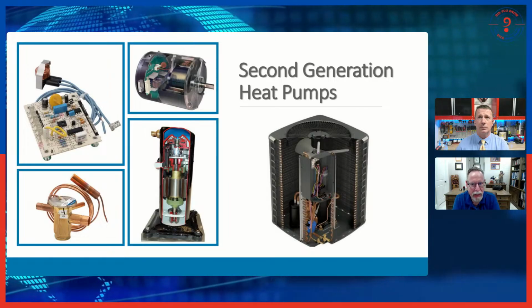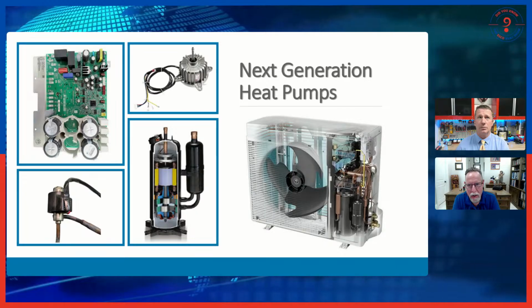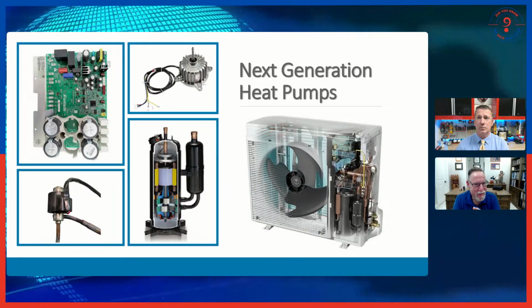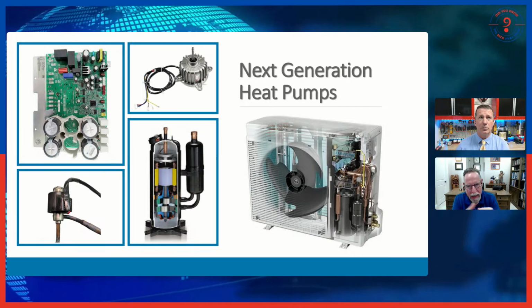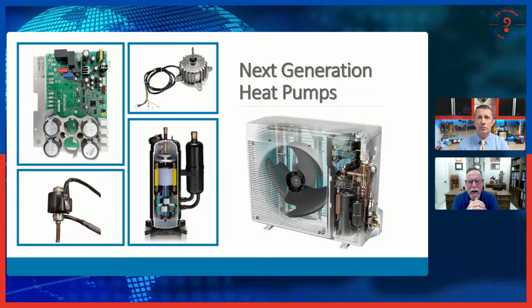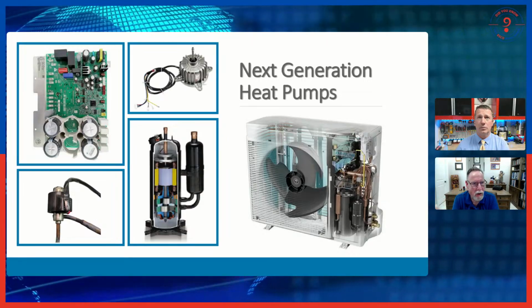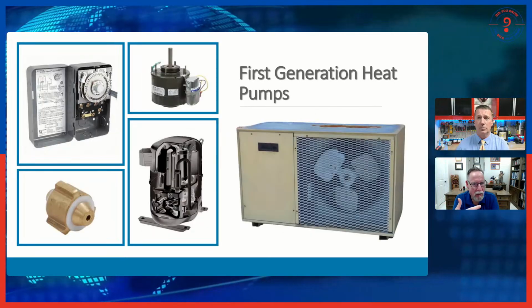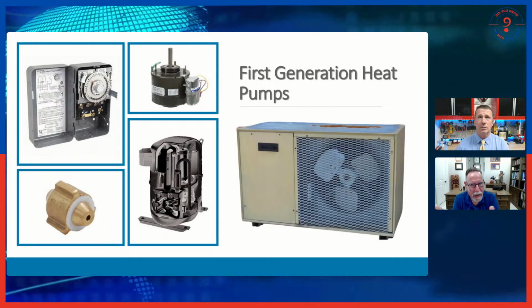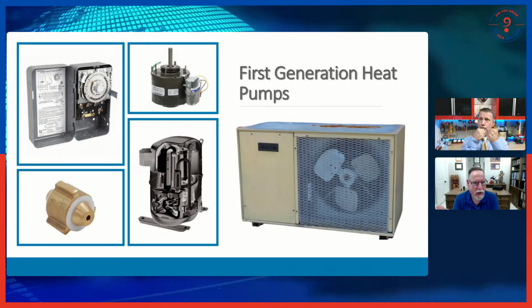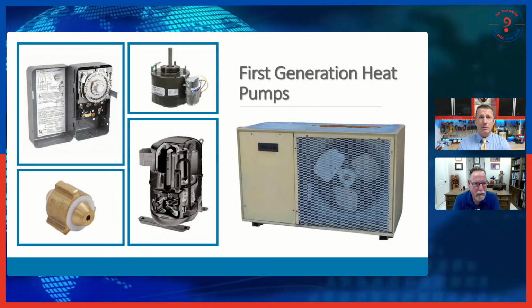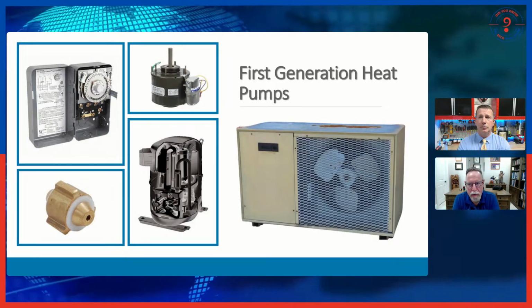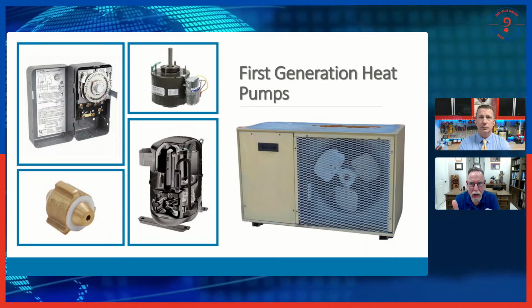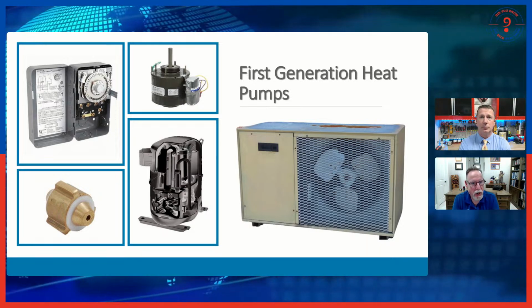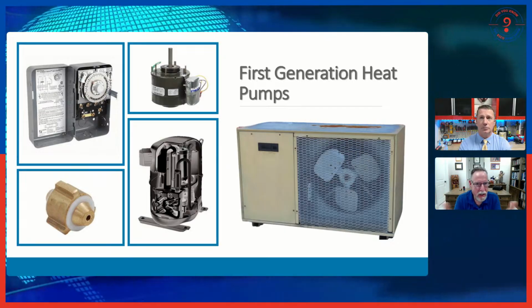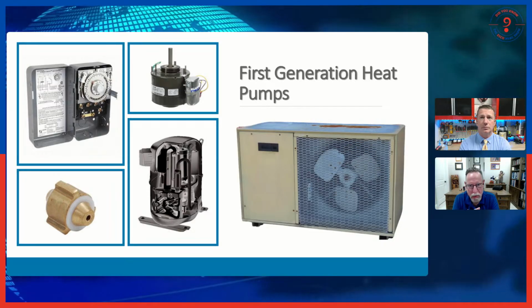Enter heat pumps that are inverter control. We now are resembling that second car we were looking at, where you're easing off the brake and gently accelerating. So think about an old PSC motor that we used to install, and we probably still see out in the field to some degree now. That motor experienced lock rotor amperage on startup, and that lock rotor amperage is roughly 5 to 7 times greater than the full load amperage of the motor. So you're experiencing that inrush of current, and excessive heat, because with the inrush current comes heat - a byproduct of current is heat. So the life expectancy of these motors was a lot shorter.